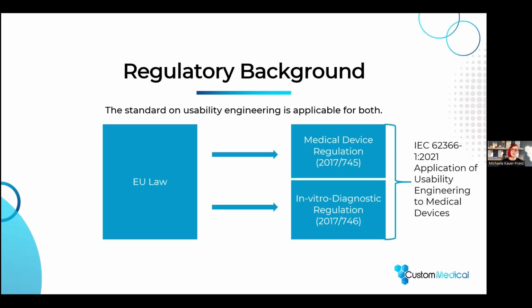For the usability engineering sector, this is especially interesting because the former standard, the 62366 from 2007, was harmonized. But because it's not up to date and it's not the best version, it was withdrawn, and no new standard is harmonized today. But in contact with all the notified bodies, this is the standard you have to look at.